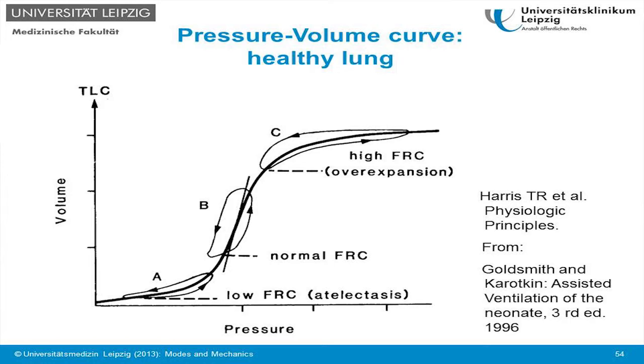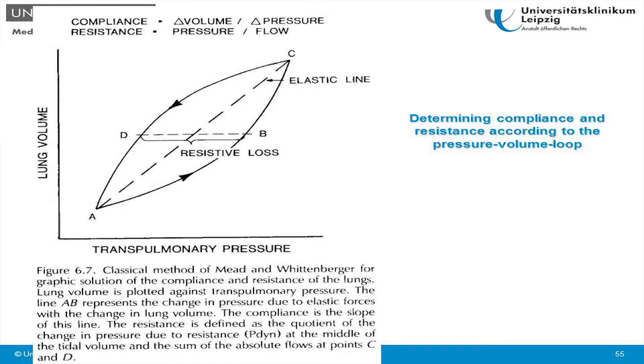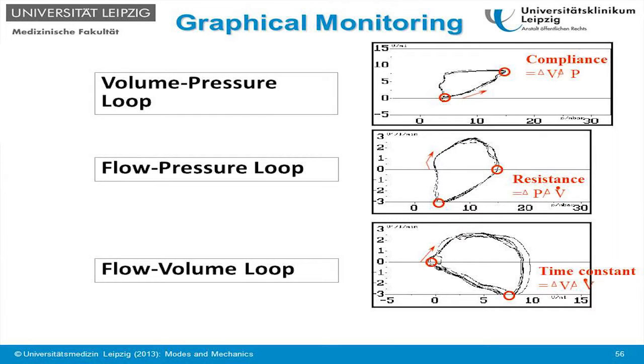You can also measure pressure volume curves of your lung and to get more information. In the pressure volume curve, the line from A to C will determine the compliance of the lung, while D to B is the resistive loss, and thereby a measure of the airway resistance. And by measuring these things, the ventilator can determine resistance and compliance of the patient and display this on the screen. If you want it more sophisticated, you can measure pressure loops and display these on the screen and gather information about the patient from the loops. The volume pressure loop is here, and the increase from this point to this point will be the compliance.